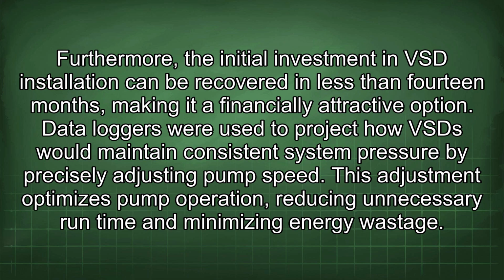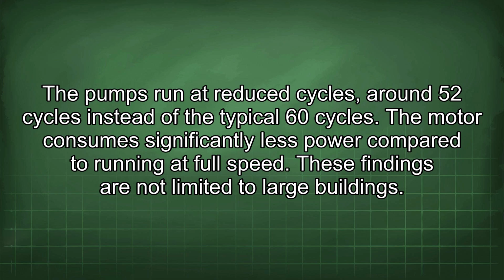option. Data loggers were used to project how VSD would maintain consistent system pressure by precisely adjusting pump speed. This adjustment optimizes pump operation, reducing unnecessary run time and minimizing energy wastage. The pumps run at reduced cycles, around 52 cycles instead of the typical 60 cycles. The motor consumes significantly less power compared to running at full speed.